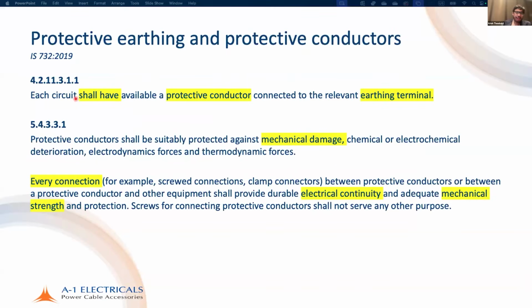Protective earthing and protective conductors have requirements. Firstly, each circuit shall have a protective conductor available, connected to the relevant earthing terminal. Protective conductors shall be suitably protected against mechanical damage, chemical or electrochemical deterioration, electrodynamic forces, and thermodynamic forces. Remember this mechanical damage and electrochemical aspect, we'll come back to it. Every connection, for example screwed or clamp connections between protective conductors or between a protective conductor and other equipment, shall provide durable electrical continuity and adequate mechanical strength and protection. Screws for connecting protective conductors shall not serve any other purpose. So it is very important that mechanical damage is protected against and there is adequate electrical continuity and mechanical strength.